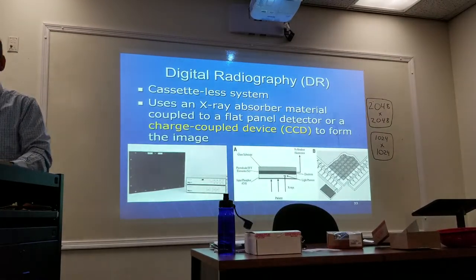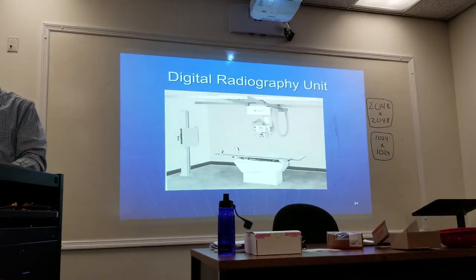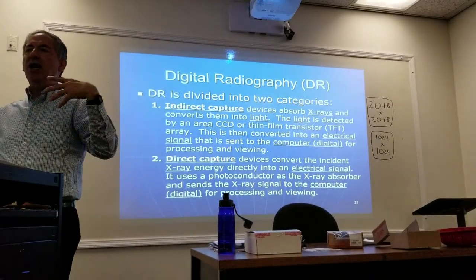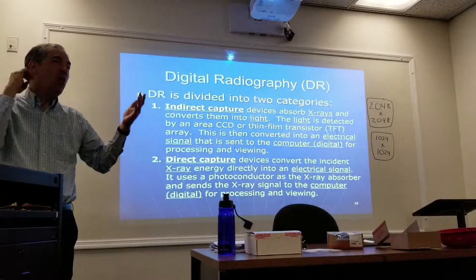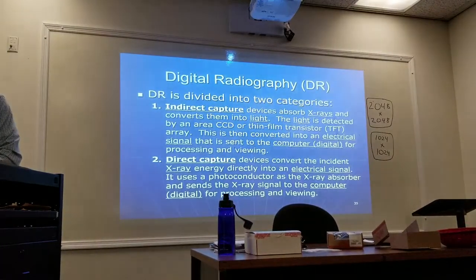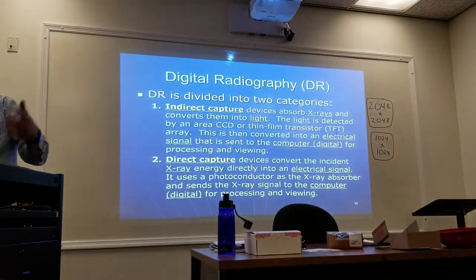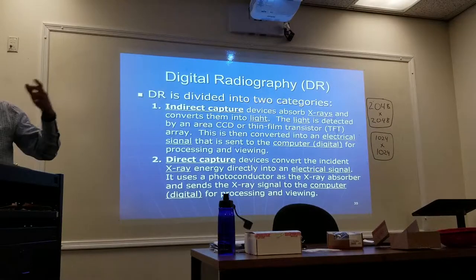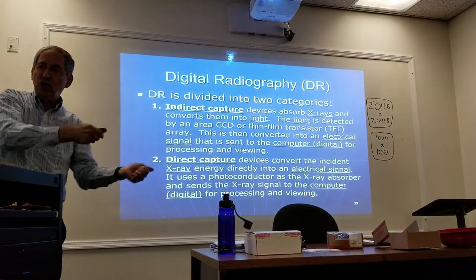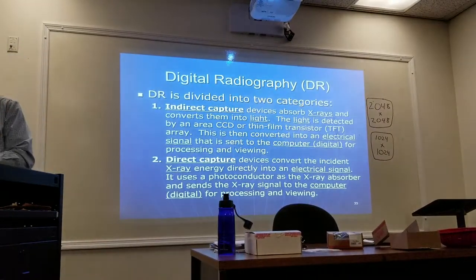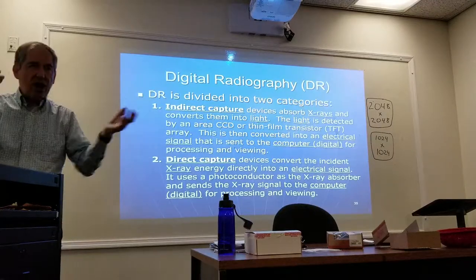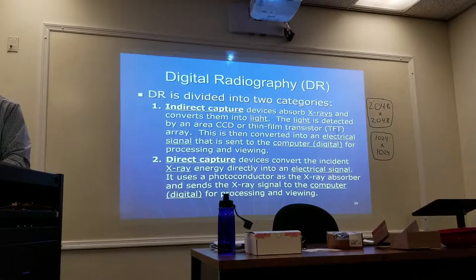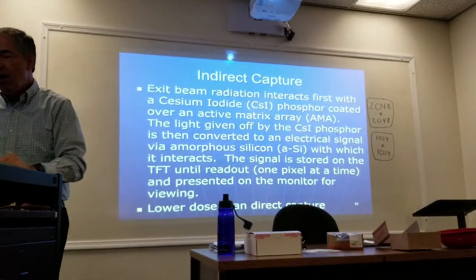DR is divided into two categories: indirect capture and direct capture. Indirect capture just adds one step more than direct. With indirect capture, it absorbs the x-rays after they go through the patient's body, converts that into light, and then the light is detected by the CCD or thin film transistor, and that's converted into an electrical signal — so it's x-ray to light to electrical signal.